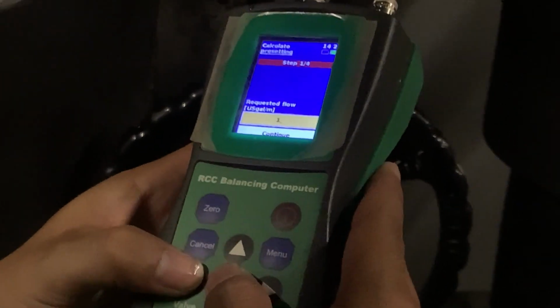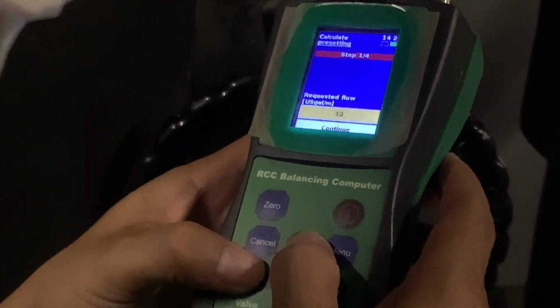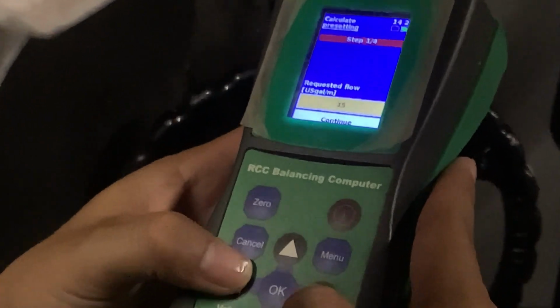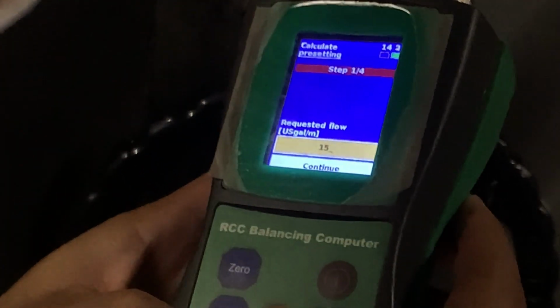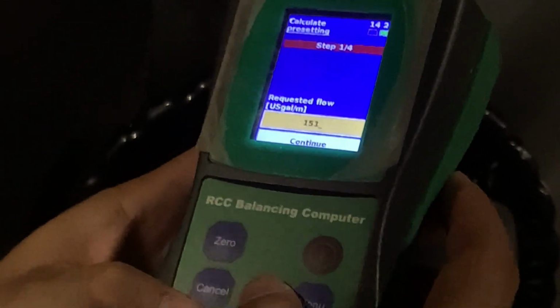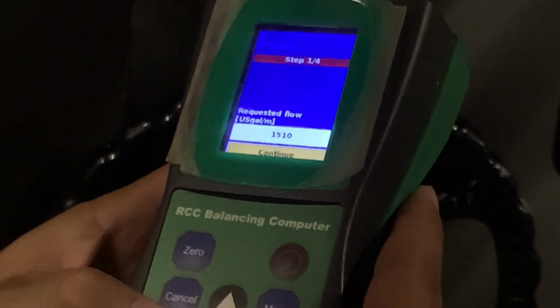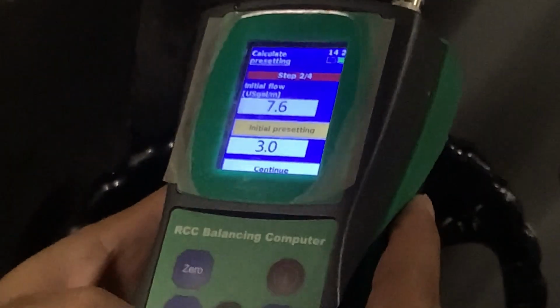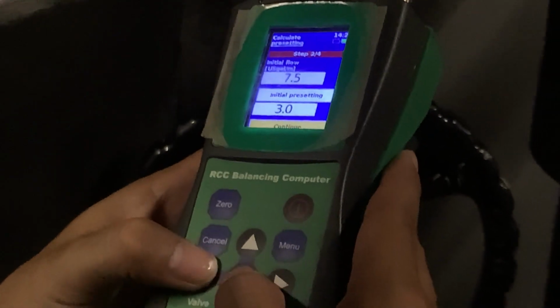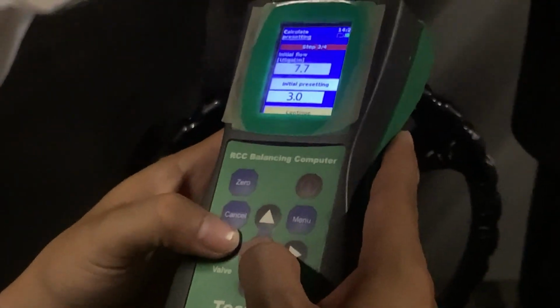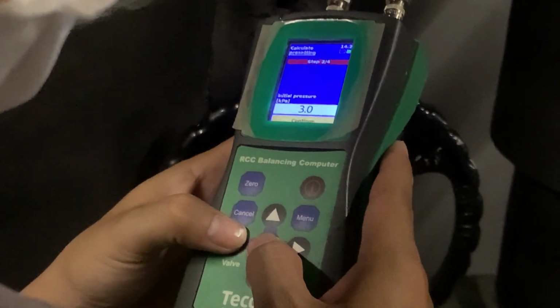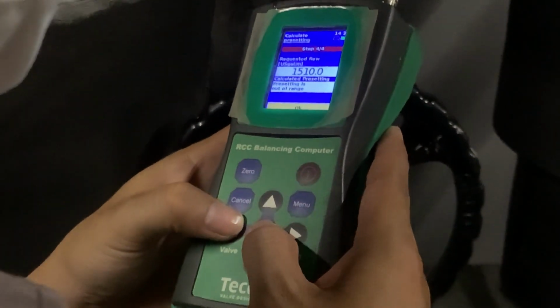Here we do the balancing from the main risers, because we want to know if the main riser has enough flow or not. If the main riser is not enough, the branch will not be enough the same. At the use point, we also have to do the balancing the same.